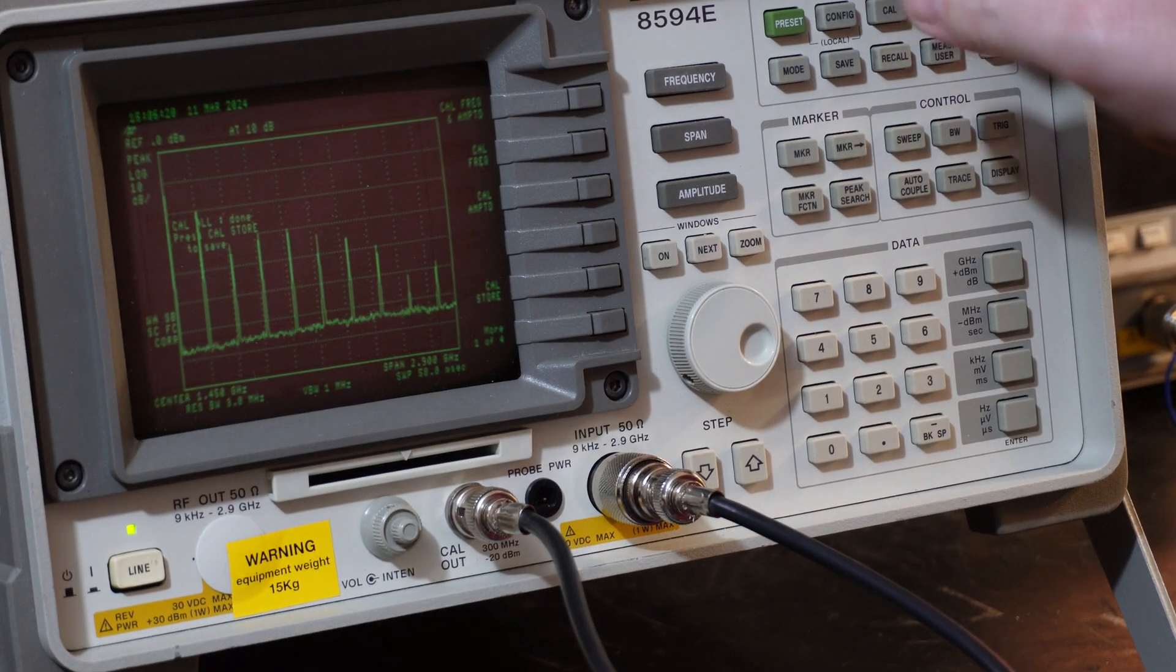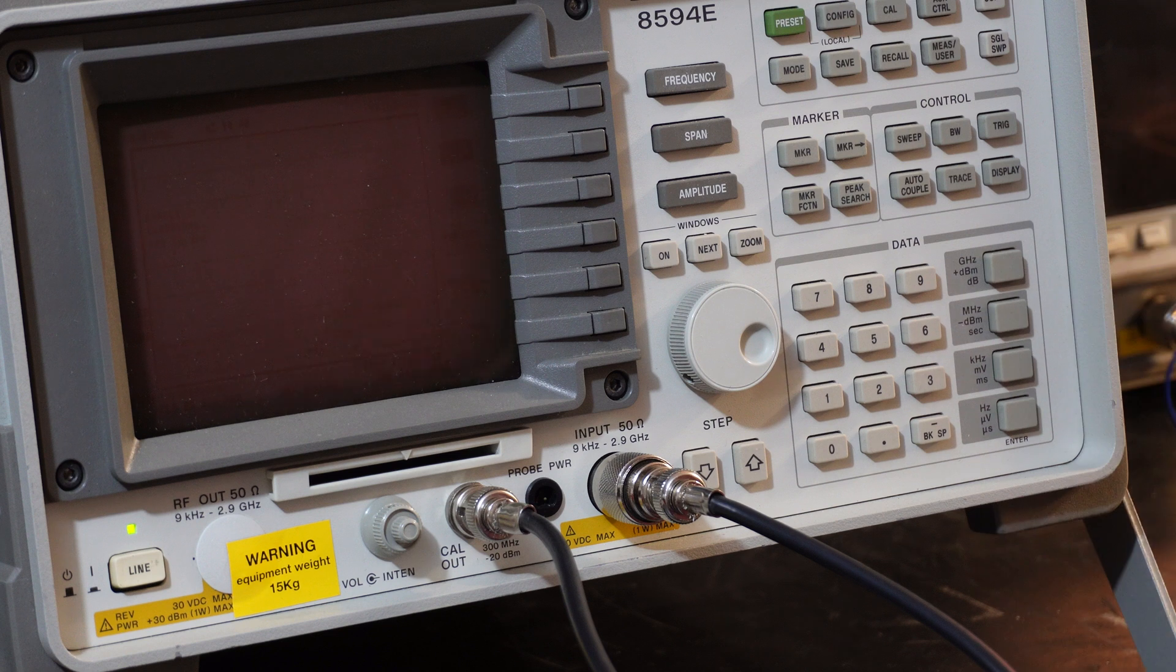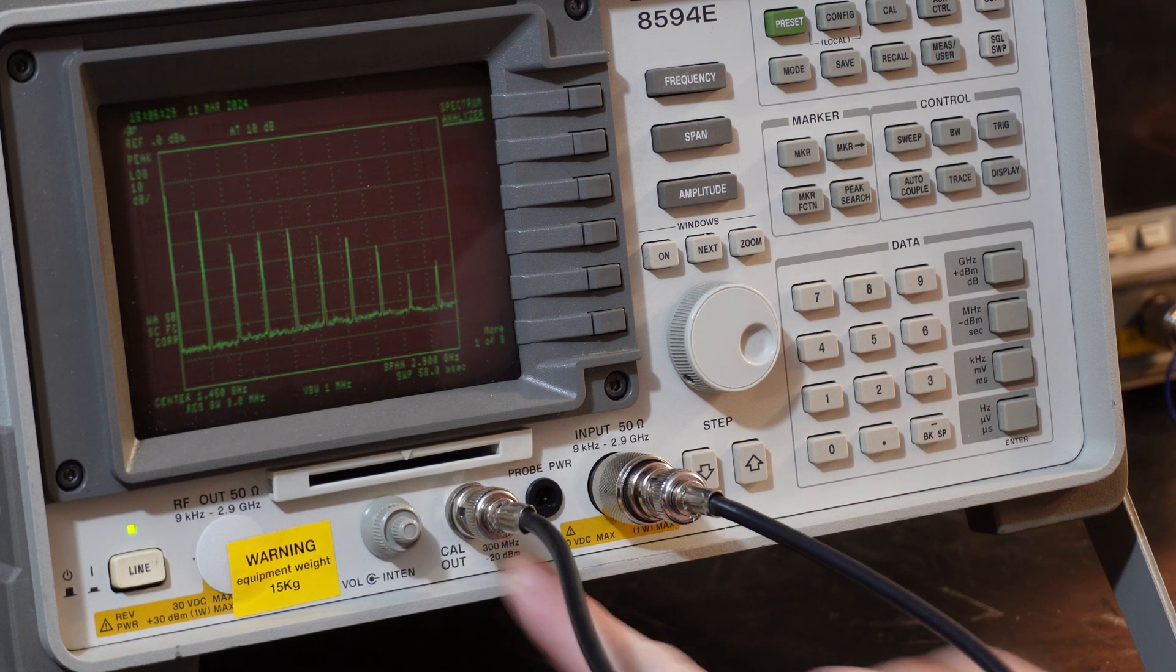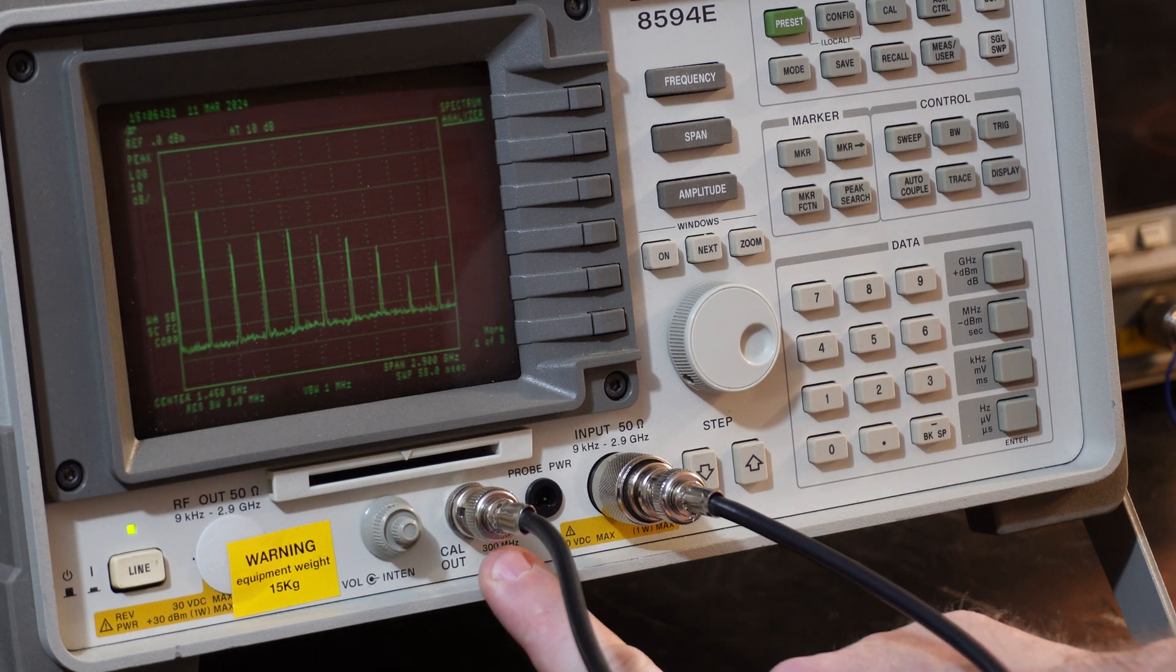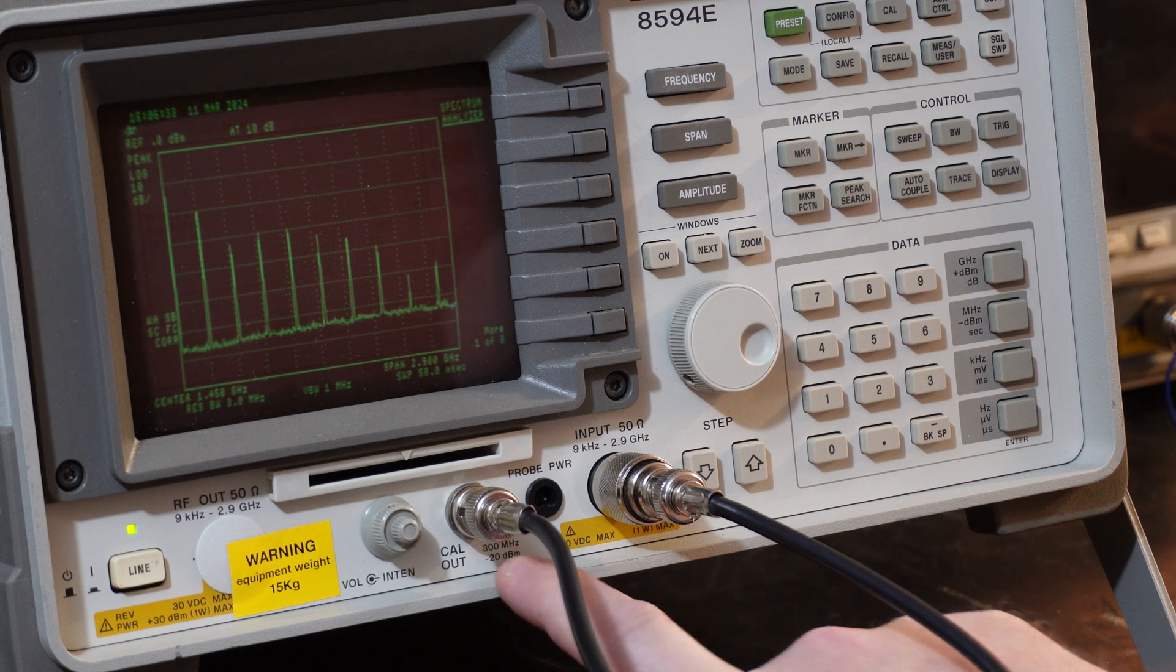Okay, so we've got her calibrated. Just hit preset to bring her back to the start. What I want to do first is measure the calibration signal. We have a 300 megahertz signal at minus 20 dBm.